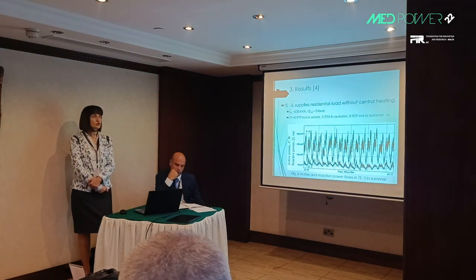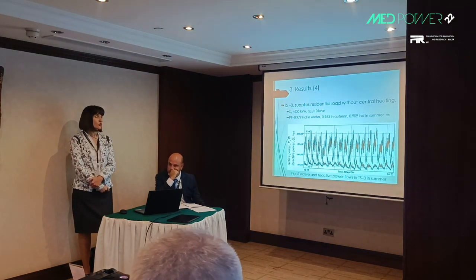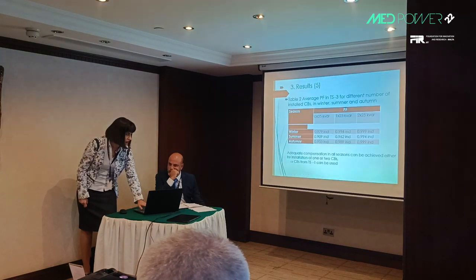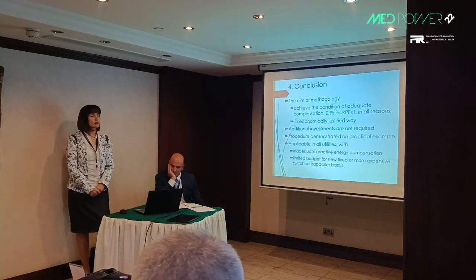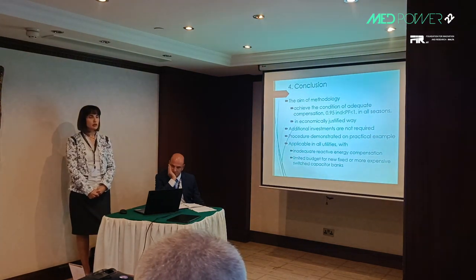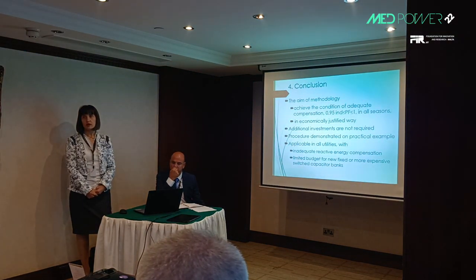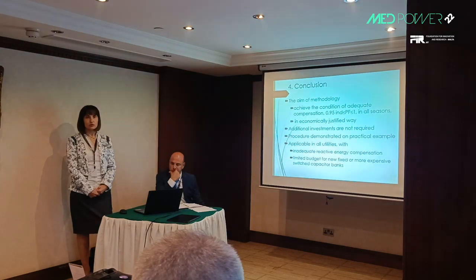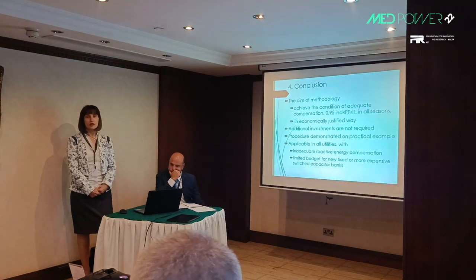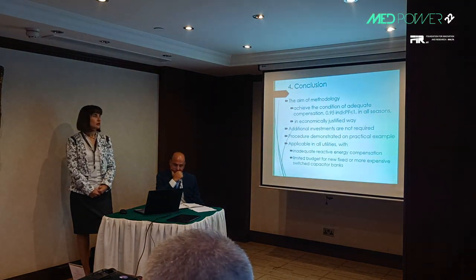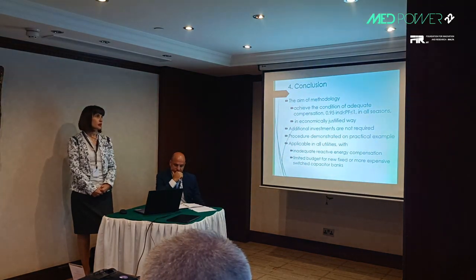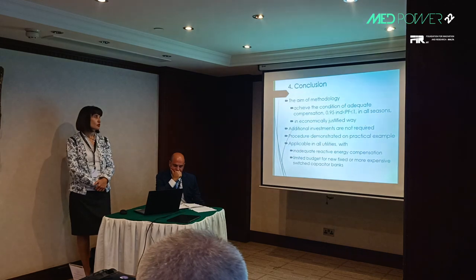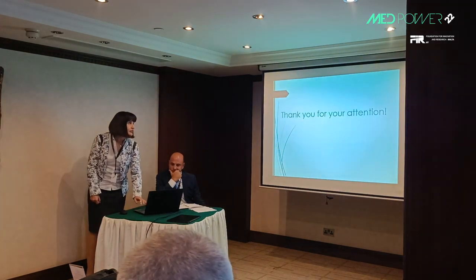Therefore, we can remove capacitor banks from transformer substation 1 and install them in transformer substations 2 and 3. The aim of this paper is to explain a methodology to improve power factor in transformer substations in an economically justified way. It is very useful for utilities which have problems with overcompensation and a low budget for installing new capacitor banks or more expensive switched capacitor banks. Thank you for your attention.